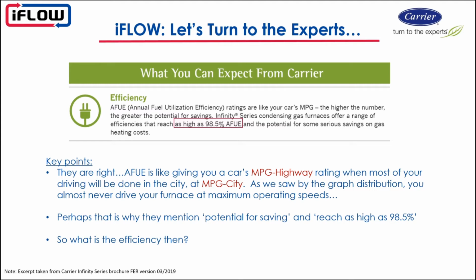It really is a matter of how you drive the vehicle or the furnace, and then it may reach as high as 98.5%. It doesn't tell you you're always going to get there, because when we're cycling at some of those lower input rates below, let's say, their minimum threshold, then you will have some cycling and the efficiency will not be as high. So then the question is, well, what is the efficiency then?